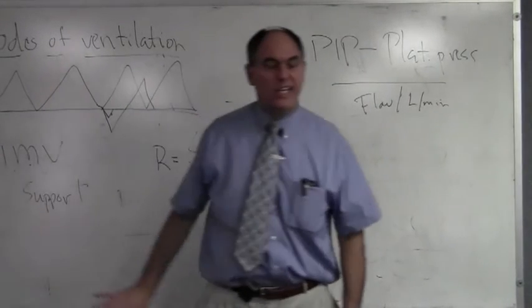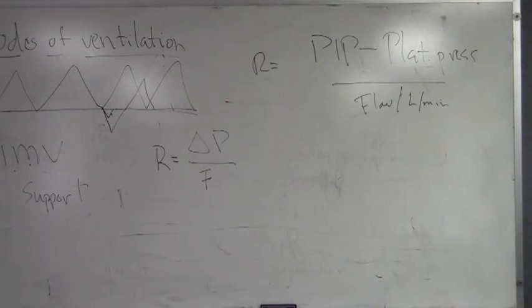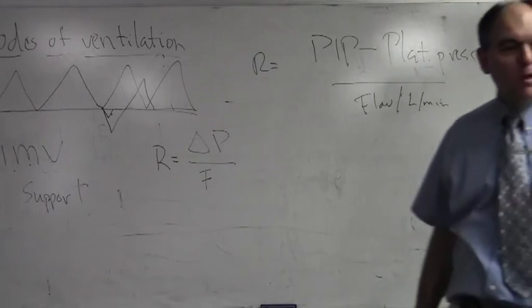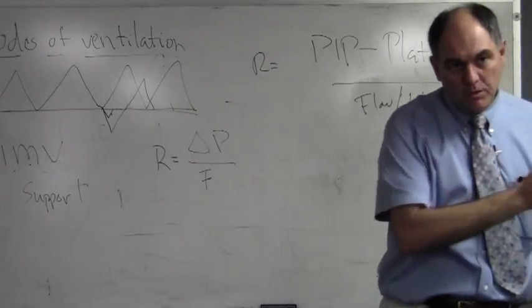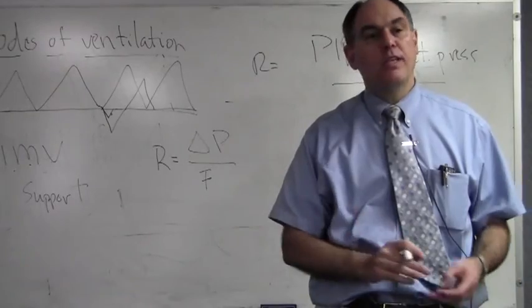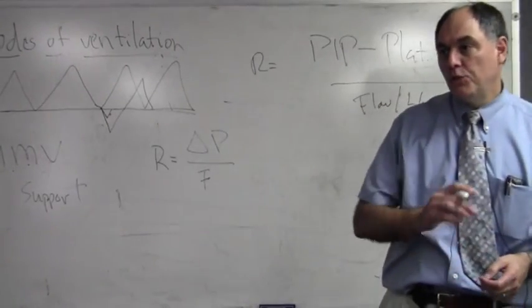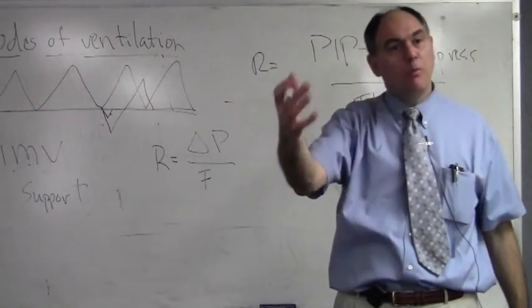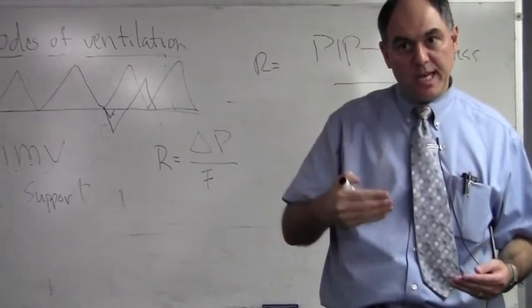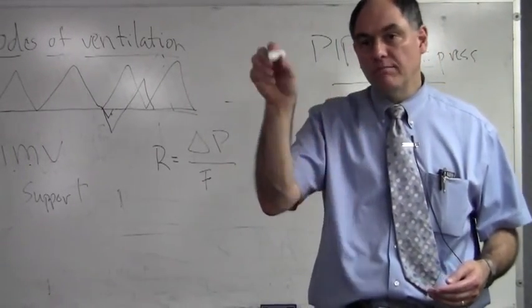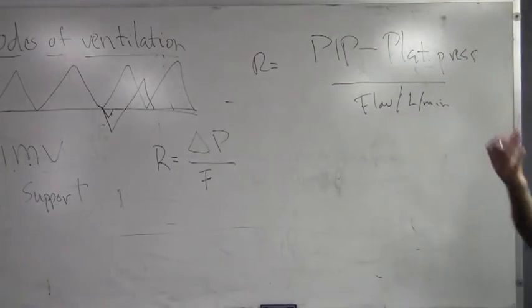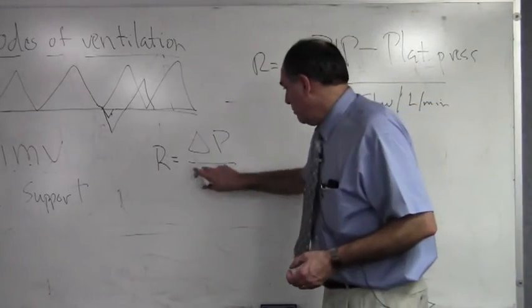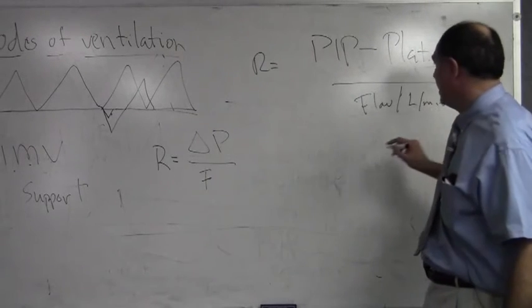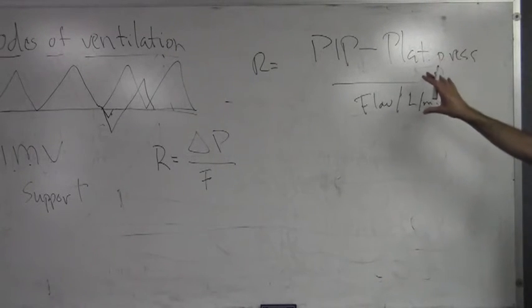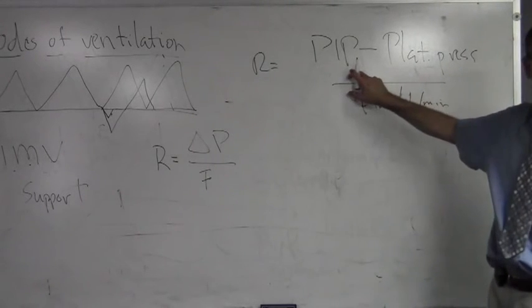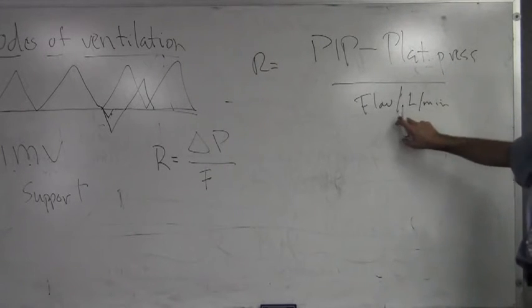We're going to go through all of the settings later, but one thing that you don't necessarily set, I look at it, but usually the respiratory therapist will set it. You can set the speed with which the oxygen is delivered, which is the flow. And usually it will go anywhere from 40 liters per minute to 100. I know you don't pay attention to that, but if you look into that green book where they give you the settings, you'll see flow, and they'll put either 0.6 or 1.00, 100, whatever it may be. And that's where the flow comes from. So if this is the resistance, all you would need to do is calculate the resistance for every individual patient by getting the peak inspiratory pressure, subtracting the plateau pressure, and the flow is given to you, right?